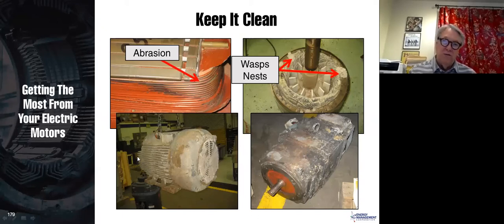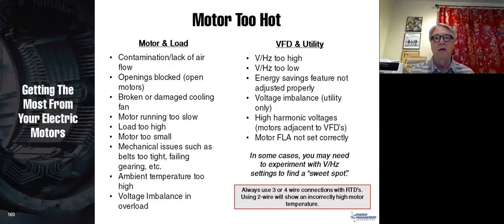You can see these fins on the outside of a totally enclosed fan-cooled motor. Really, we need to keep that stuff cool. If those fins get blocked up, then the motor's going to run hot because they need that in order to cool themselves. If your motor is running too hot, here's a little checklist you can go through and ask yourself all these questions to see if one of those things is causing your motor to run too hot.